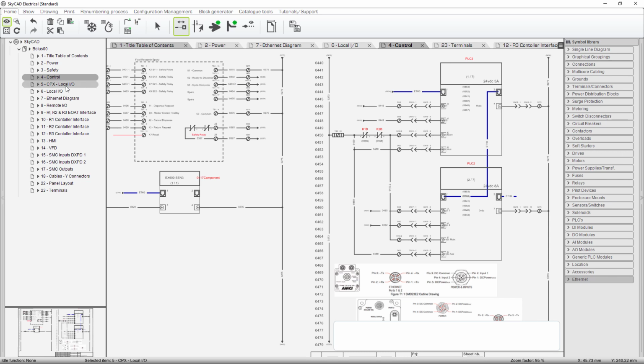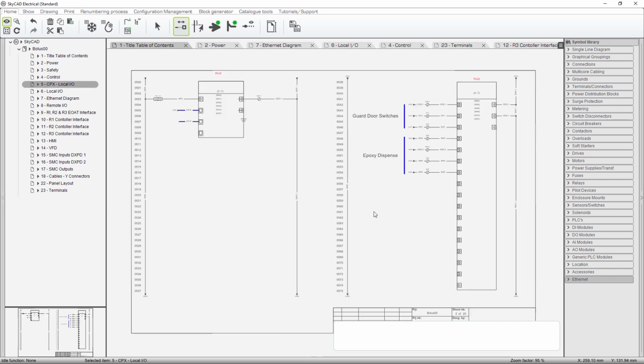Those go to inputs here. Now I'm showing 4, but remember I didn't have 4 outputs from the epoxy dispense to the controller, the input module. But I'm showing 4 connections because I want it wired up that way. So if I want to add something from epoxy dispense into this controller, the wire's already there. I just have to program it.